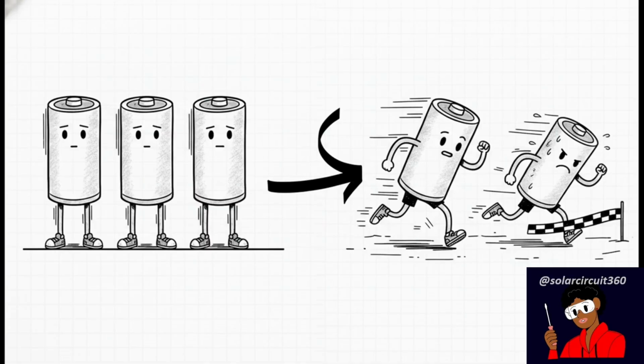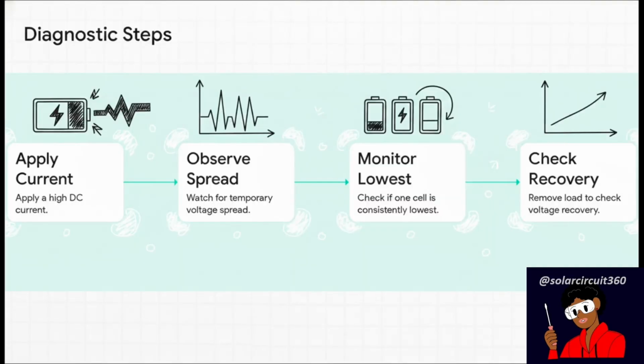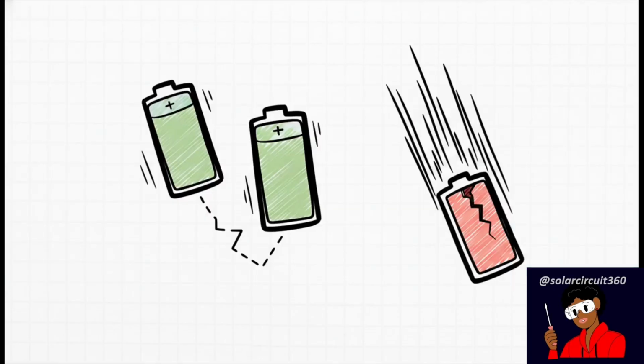It just means their bodies handle that intense stress slightly differently. So, how do we actually use this information to diagnose our setups? Well, we don't just stare at a resting battery. We run a 4-step check. First, apply a really high DC current. Second, watch how wide that voltage spread actually gets. Third, and this is the big one, monitor the pack to see if one specific cell is consistently the lowest. And finally, step 4, pull the load off and watch how those voltages recover.